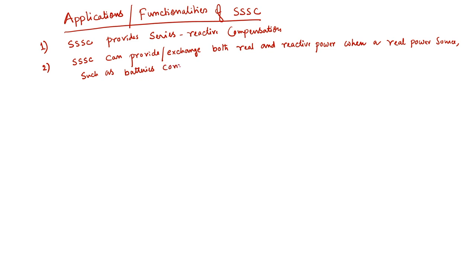connected to the DC link of SSSC. So, this is eventually effective. I will come to that why it is so. In fact, you have already seen that series reactive compensation is somewhat more effective as compared to the shunt reactive compensation, in the sense that if you want to enhance the steady state power transfer capacity, the series compensator can do so with reduced rating.